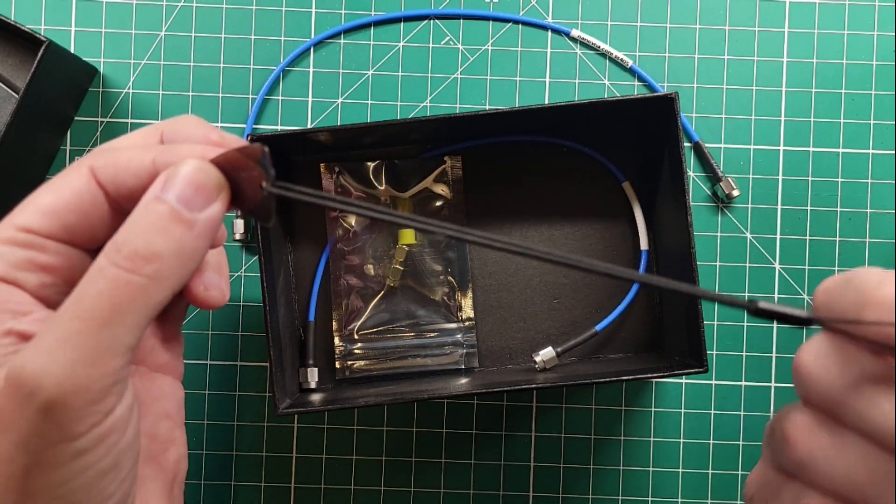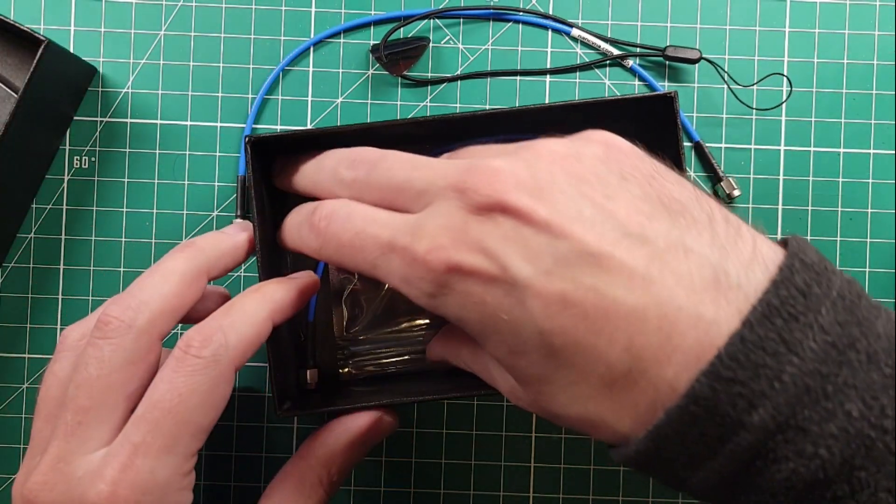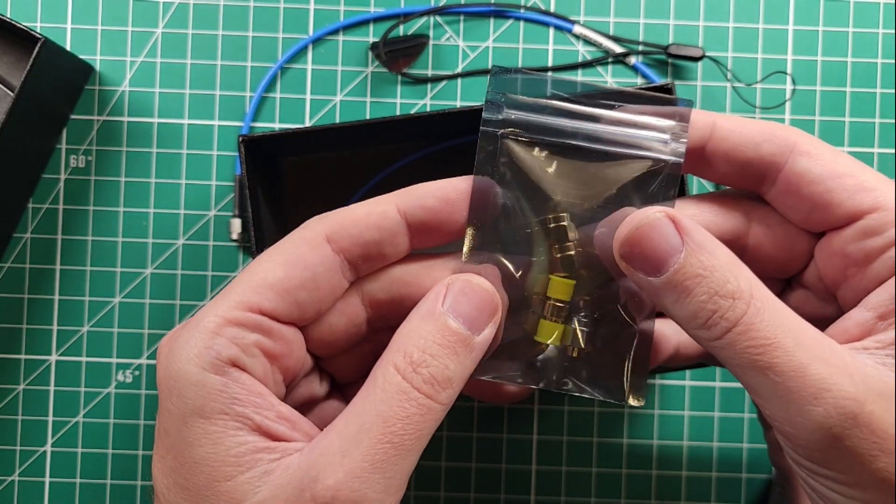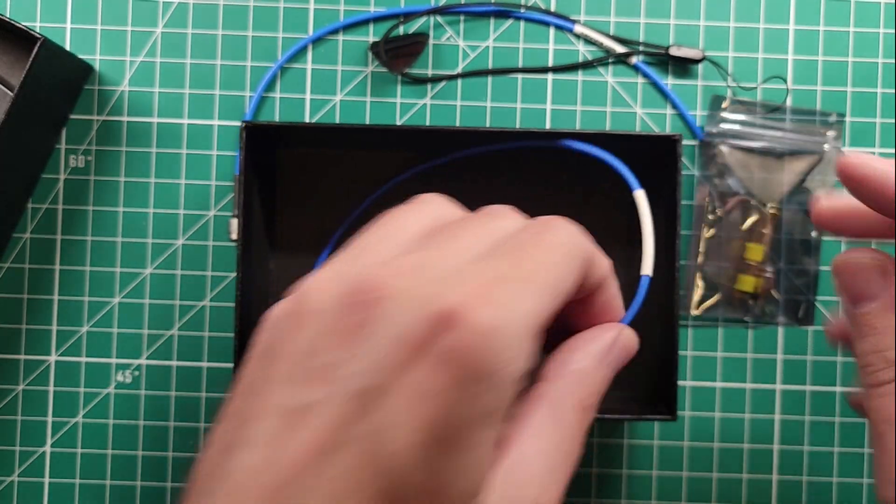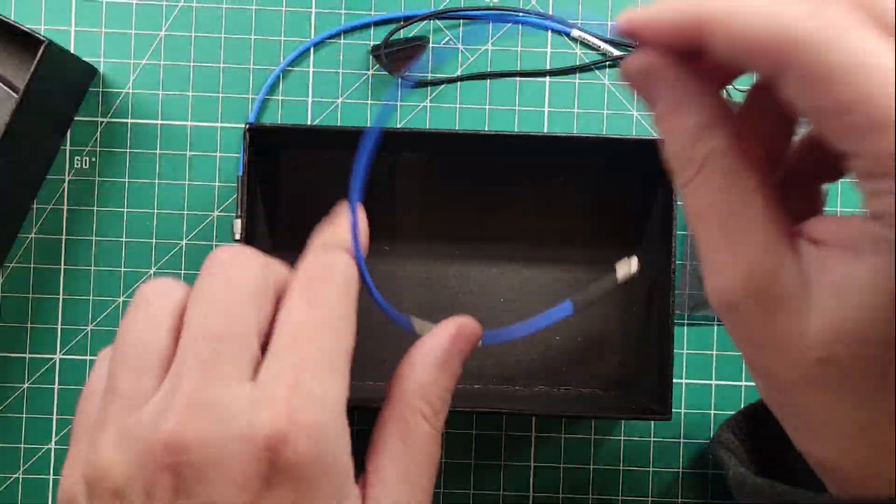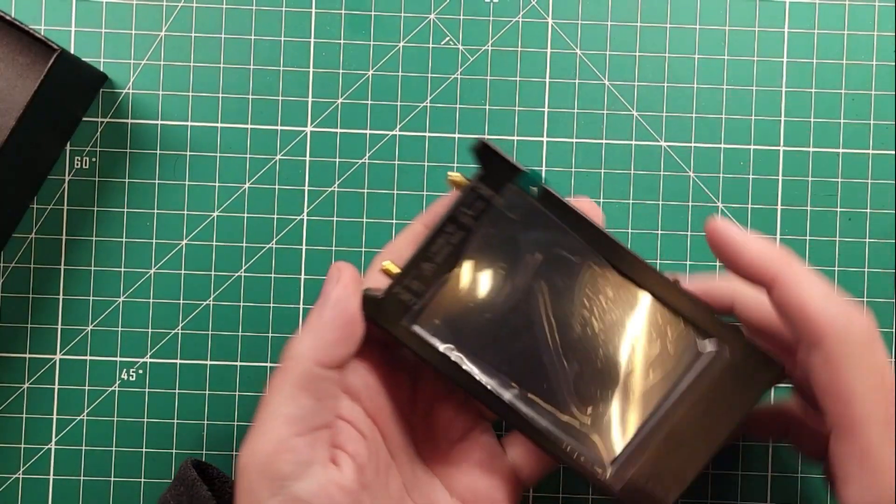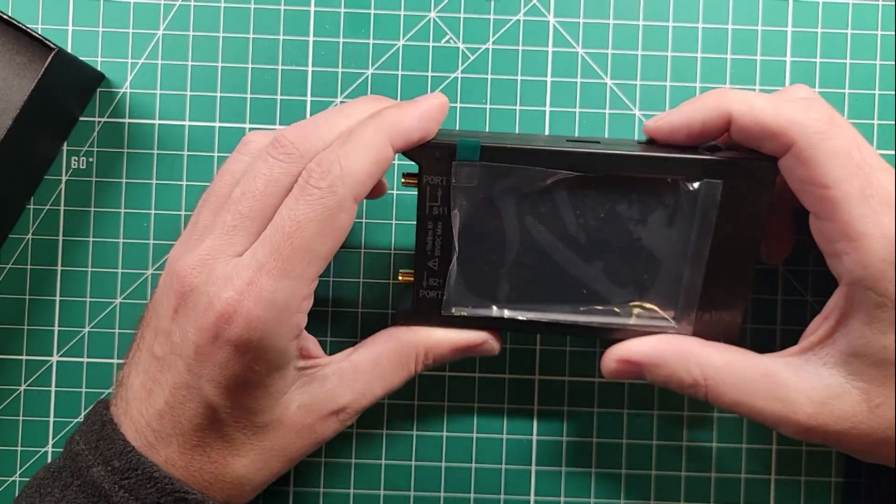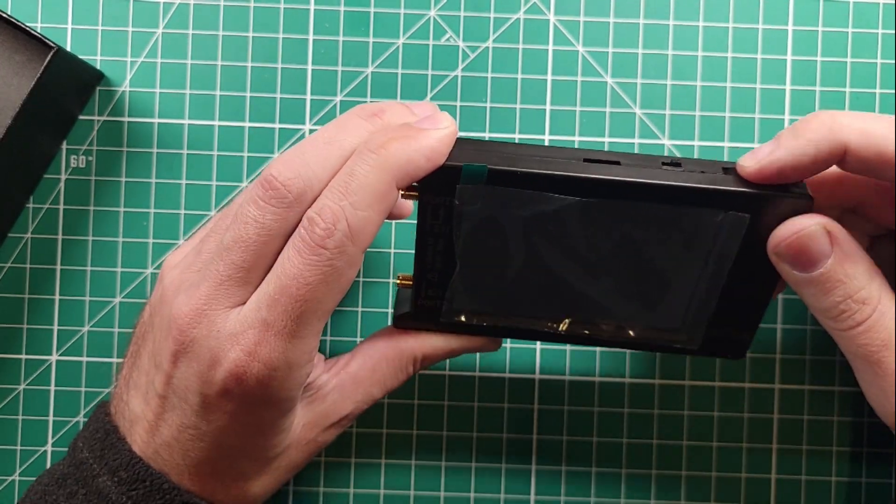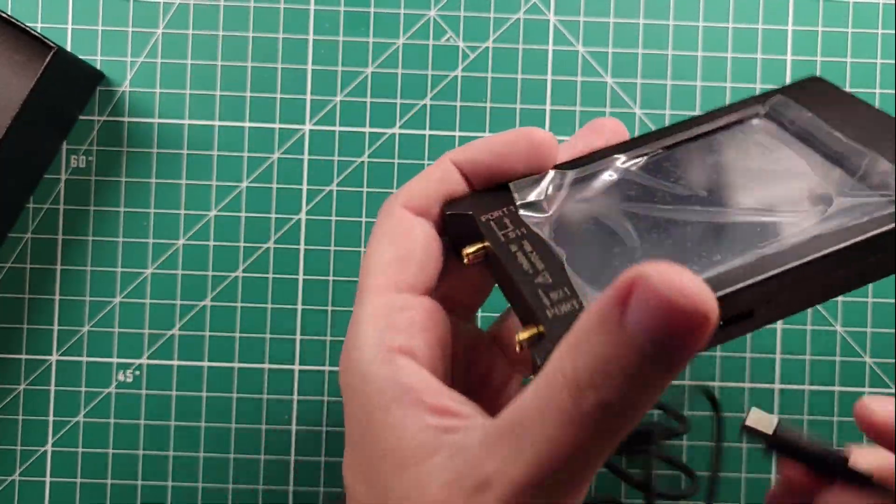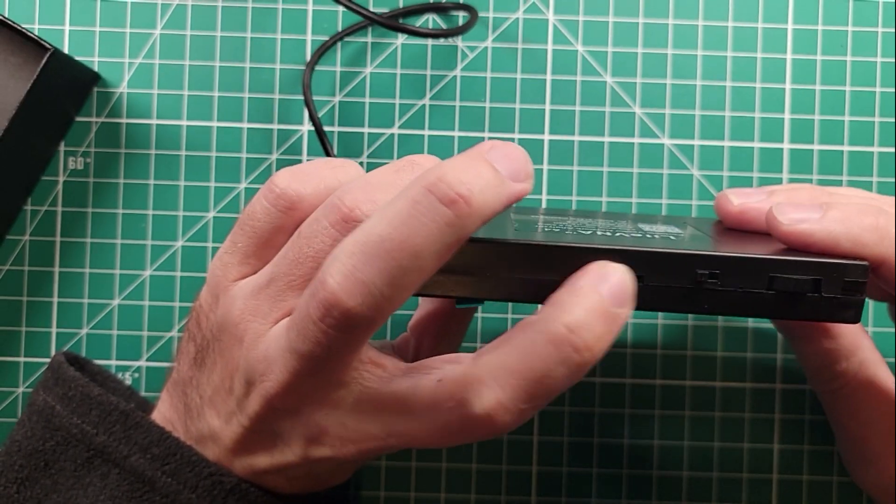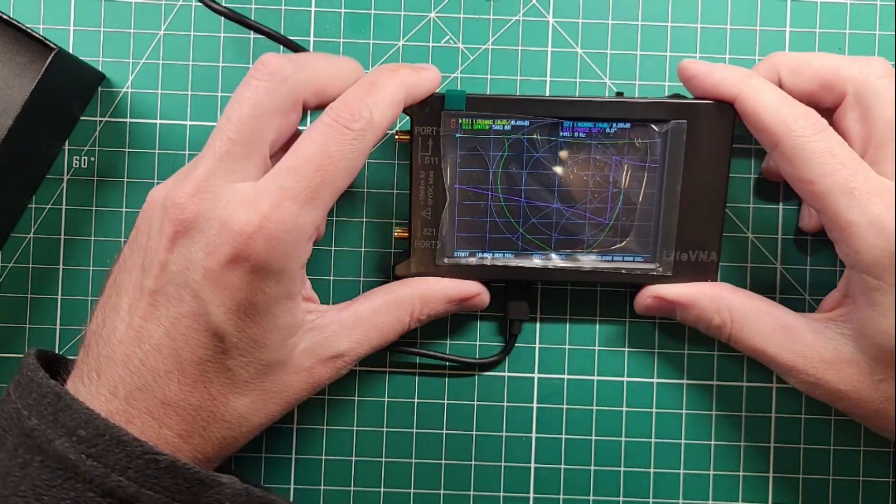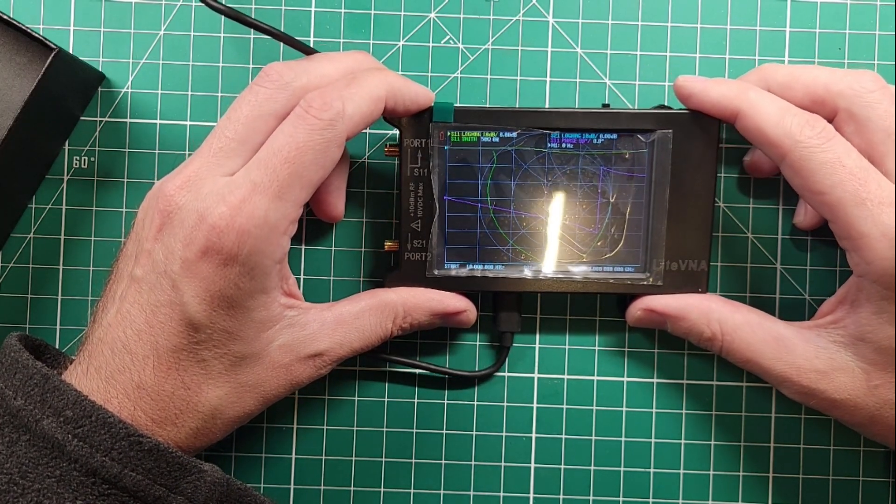And then you have your stylus device. I use this quite a bit because I don't like getting fingerprints on my screen. And then you have your standards. So the typical short open load and then the union connector for when you do through testing so that you can calibrate out the magic of these wires. No battery charge. Plugs on the bottom of this one. All right. So we've got it plugged in and we have a little red light shining through the top here. Is that going to give us some juice to turn it on? That is going to give us some juice to turn it on. It doesn't look too terribly bad on camera.